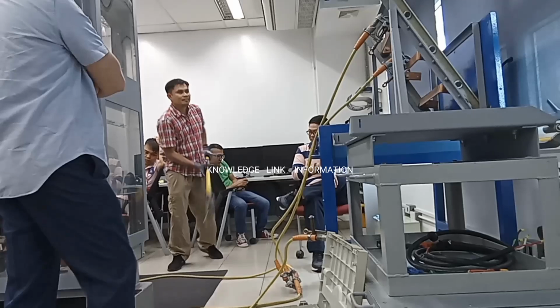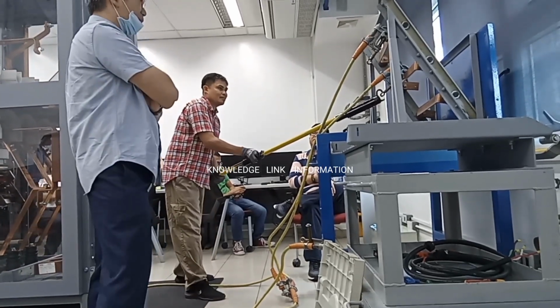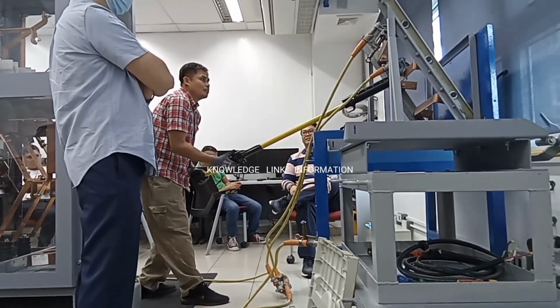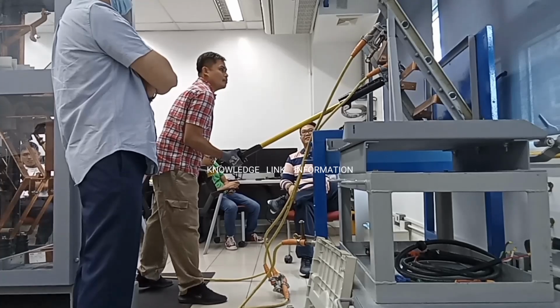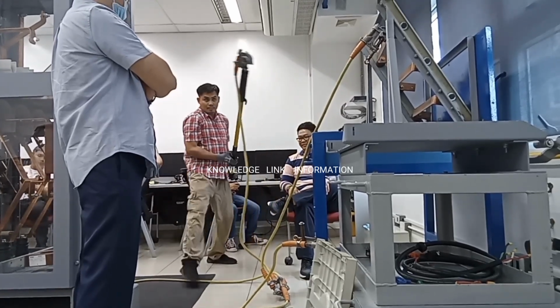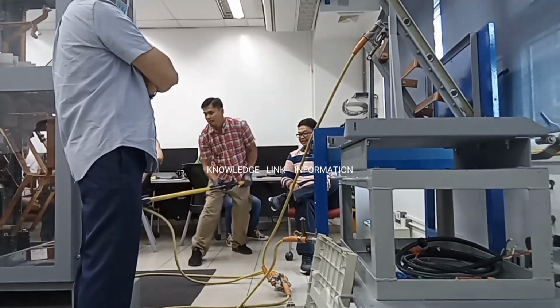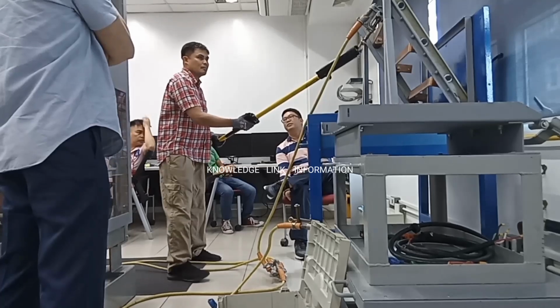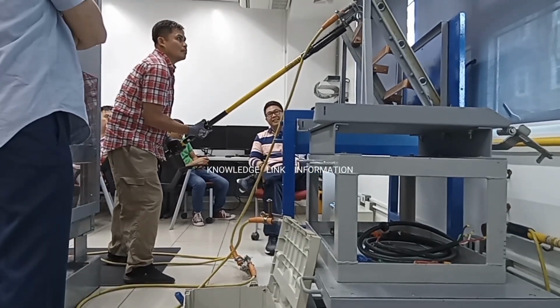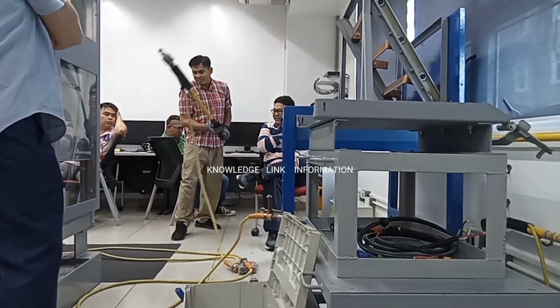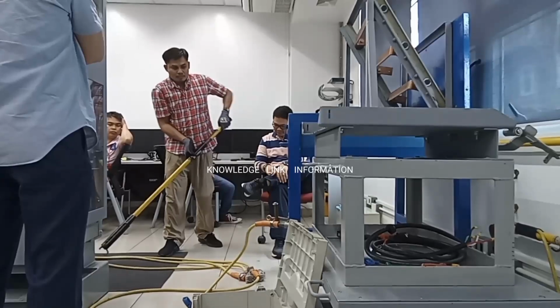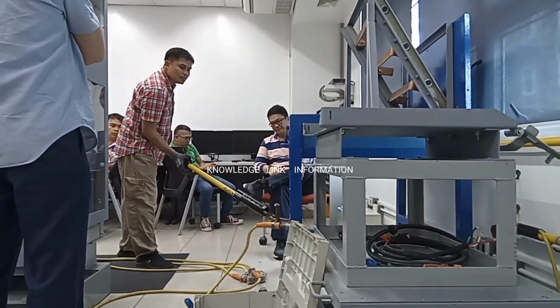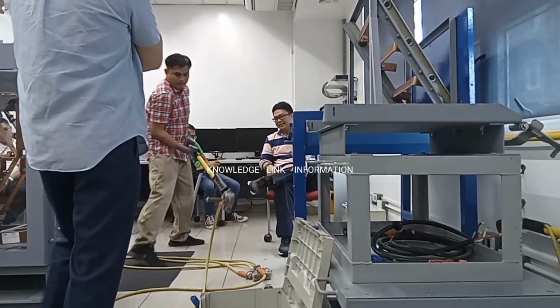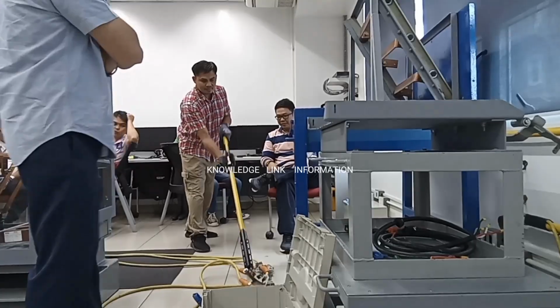Number 20. Remove the next connection clamp on the second phase of the bus bar, and gently put down the clamp to avoid any damage. Number 21. Also remove the connection clamp on the third phase of the busbar. Number 22. Remove the last ground connection clamp that is attached to the conductive ground surface.